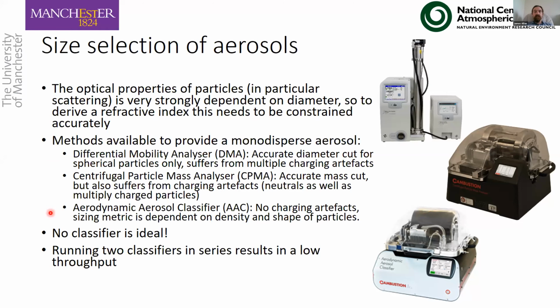And then finally, we enter the Aerodynamic Aerosol Classifier. I'm not going to go into how this instrument works. I'll direct you to Cambustion for that. But the key thing here is it selects particles aerodynamically, but it does not rely on charging. That way we don't get any of these charging artifacts. Some people have used the approach of running two classifiers in series, but that hits your throughput.